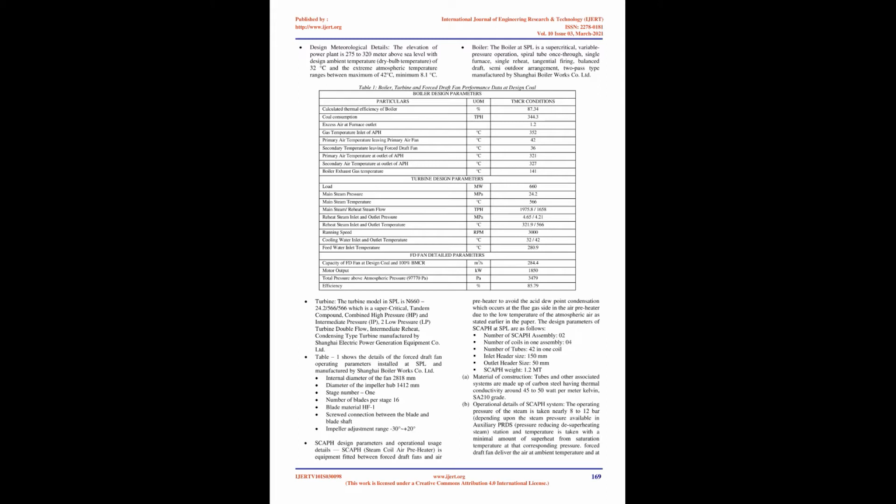To increase the efficiency of the boiler, SCAPH is introduced before the air preheater. In SCAPH, the low temperature ambient air is heated by low pressure steam to avoid cold end corrosion. Apart from that, preheating combustion air by usage of SCAPH during unit light up aids in reduction of fuel oil consumption by enabling operators to take pulverizers early.